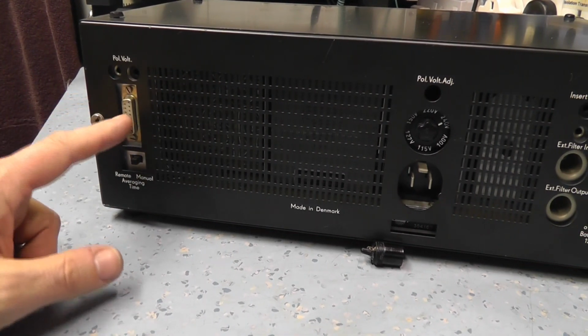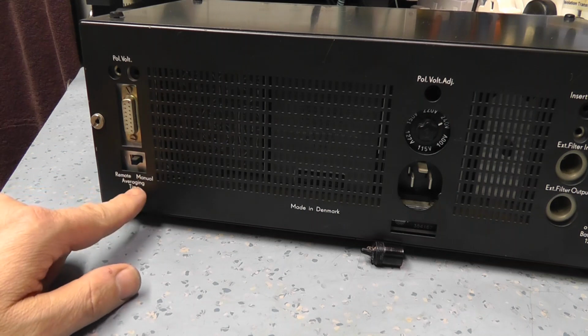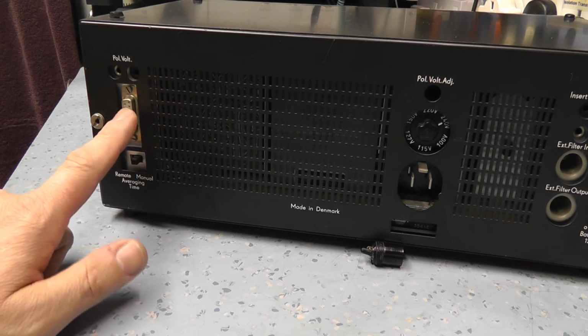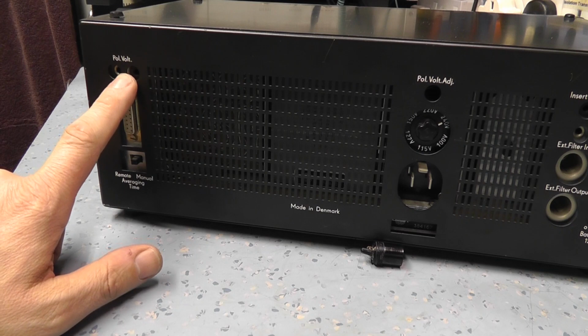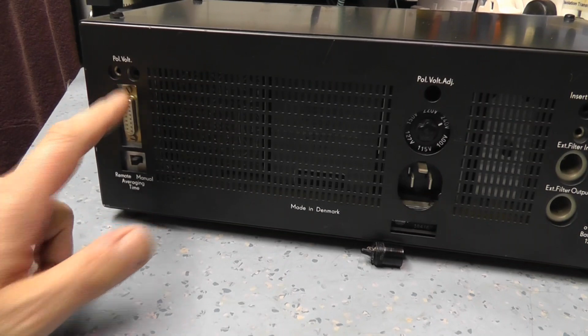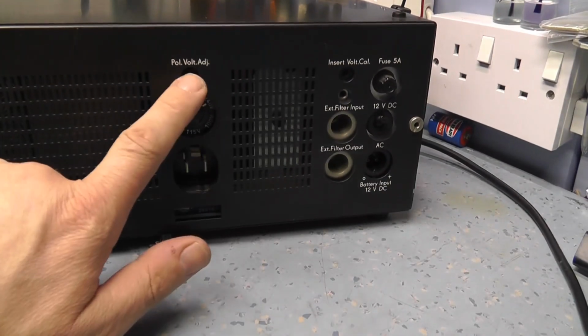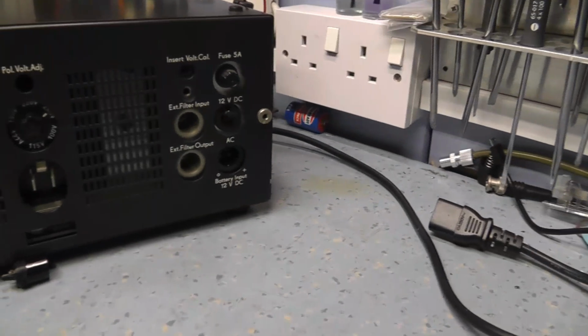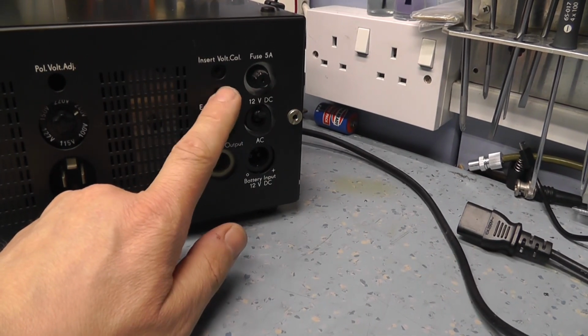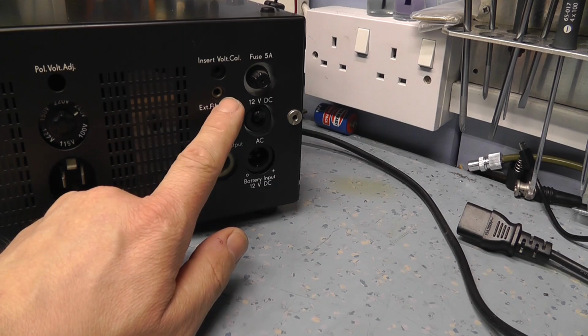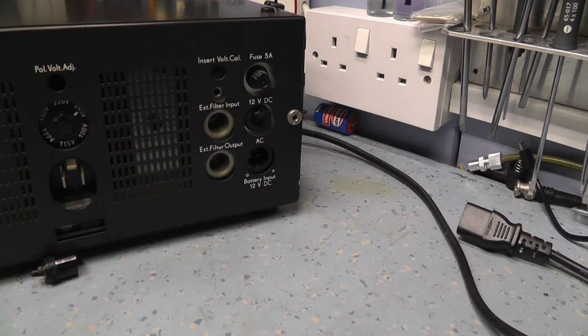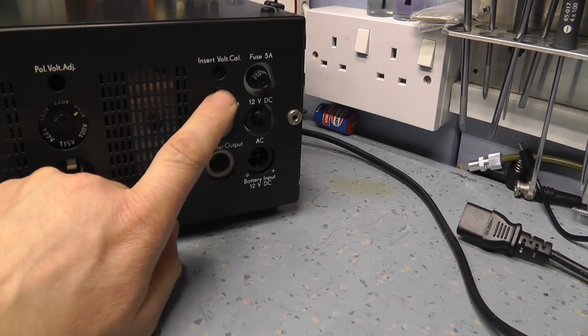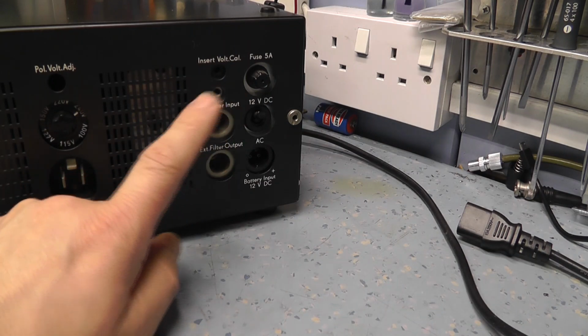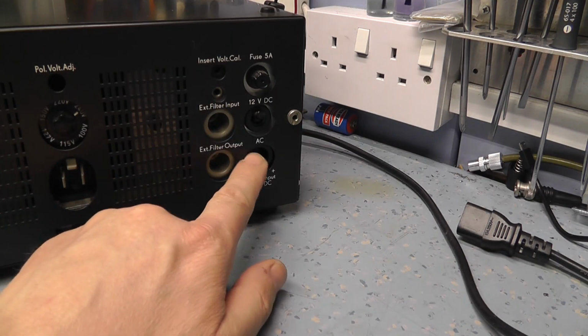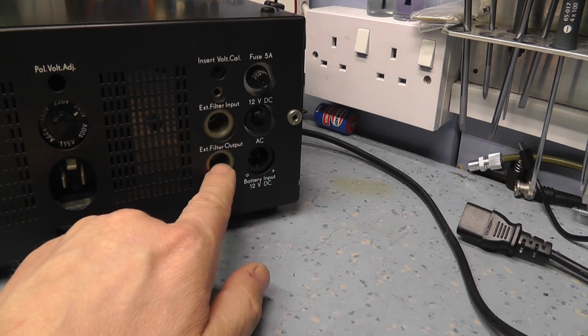This here is basically a remote control, I think, as far as I can tell. There's a switch here for remote averaging, and that I think is your voltage input, reference voltage input. I'm not sure. No, maybe not. I'm not entirely sure what that does. This is a trim pot for adjusting calibrations from what I remember in the manual, and this is our voltage calibration. So we put a calibrated voltage in here, it should read correctly on the meter, so we could connect this up to one of our process meters and just confirm the output.